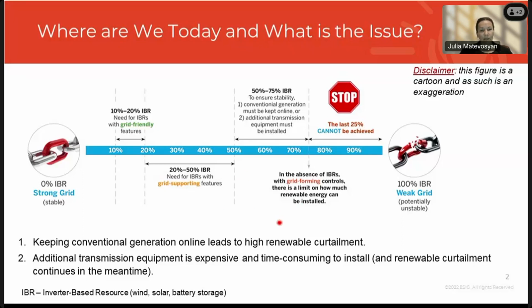And so what is being done today is that conventional generation is kept online. So you'll see constraints such as we need to keep so many synchronous generators online to operate stably. Or additional equipment is being installed, such as addition of transmission lines to reduce electrical distance to stronger voltage source, or addition of synchronous condensers. And so in the absence of more advanced controls from inverter-based resources, there is either a technical or economic limit of how much inverter-based resources can be integrated. So either it becomes prohibitively expensive with all the additional equipment that we need to put in place to support higher shares of IBRs, or there is a technical limit and we cannot just go any further.